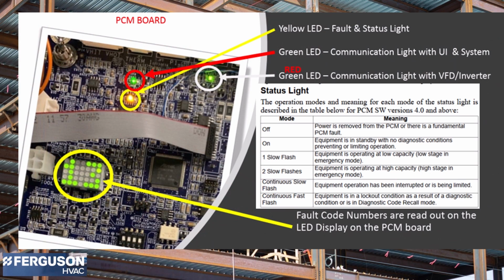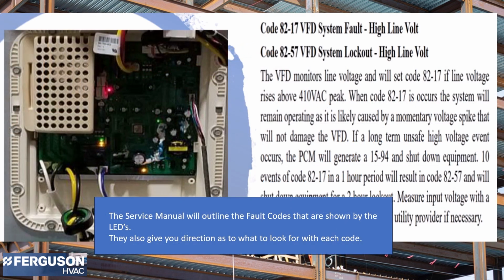All of your Carrier Bryant inverter product also have a control board that is usually located below the inverter panel. These control boards also have LEDs that will tell you what the status is of the equipment and what the fault code is. On current product, there's also a readout of the number of the fault code that scrolls across the readout on the control board. The service manual will outline the fault codes that are shown by the LEDs. They also give you direction as to what to look for with each code.